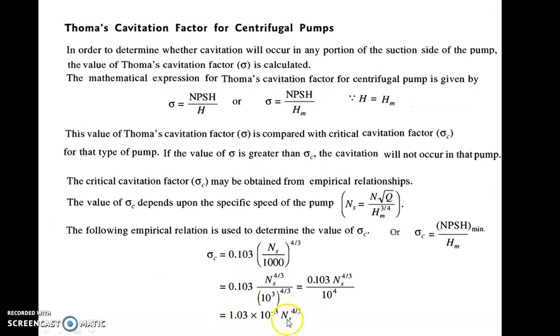Our aim is to find sigma c, and I have given you that sigma c is calculated from the empirical relation 1.03 into 10 raised to minus 3 into ns raised to 4 by 3. So if you put the value of ns in this equation, you will get the value of sigma c. But how will you calculate ns? To calculate ns, you should remember this formula: N root Q upon Hm raised to 3 by 4. If you put the value of Q as 0.16 meter cube per second, N as 1000 rpm, and Hm as 30, you will get ns.